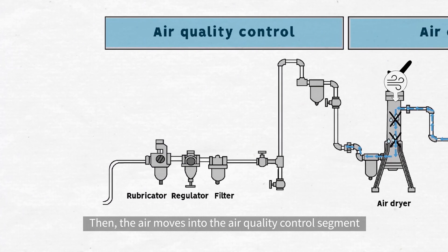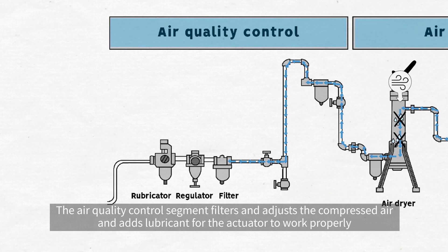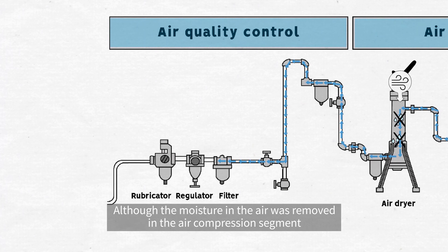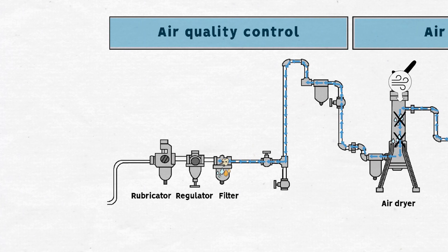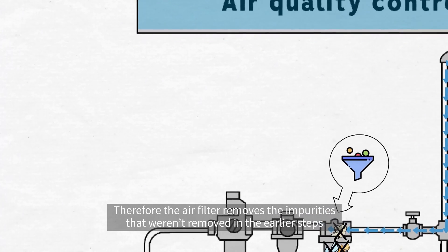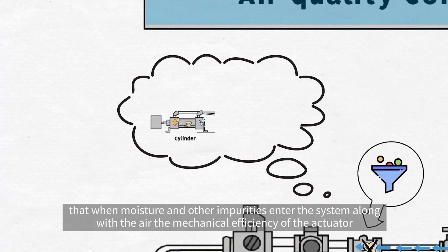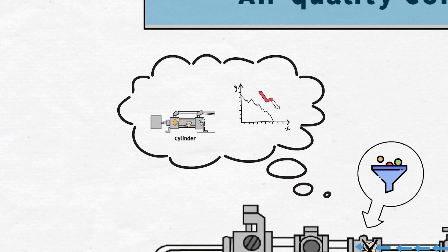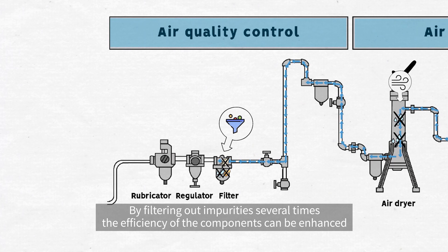Then, air moves into the air quality control segment. The air quality control segment filters and adjusts the compressed air and adds lubricant for the actuator to work properly. Although the moisture in the air was removed in the air compression segment, there still remain many impurities in the air such as oil, dust and residual moisture. Therefore, the air filter removes the impurities that weren't removed in the earlier steps. The reason impurities are continually removed is that when moisture and other impurities enter the system along with the air, the mechanical efficiency of the actuator and the lifetime of the machine will be reduced. By filtering out impurities several times, the efficiency of the components can be enhanced.